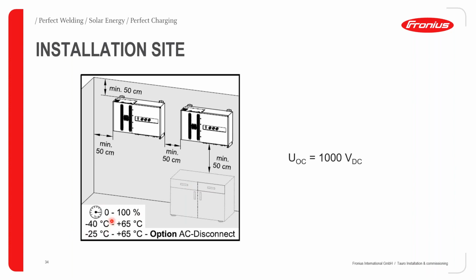In terms of the permitted humidity that the Tauro is allowed to be installed at, you can install it in any humidity levels of between 0 to 100%. So you can install this inverter at the coast perfectly fine, nothing's going to rust. So you will not have any issues on that. Also, in terms of the ambient temperature, it is allowed to install the Tauro from an ambient temperature of minus 40 degrees Celsius up to 65 degrees Celsius. So this Tauro can be installed in the Kalahari Desert and you will get extremely good performance values.